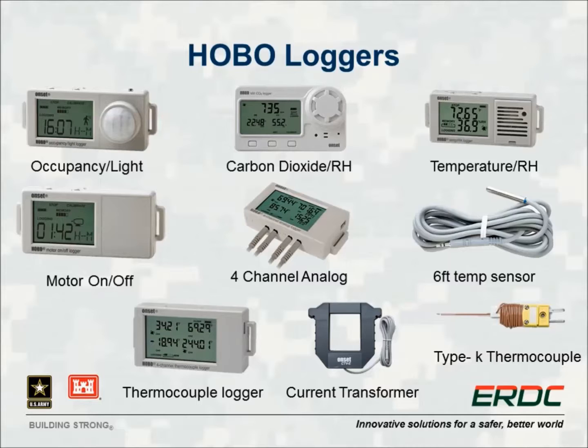It's relatively straightforward to do a study to ensure it's working correctly using a separate set of sensors, not the ones currently integrated into the building which may have their own faults, but sensors that have been recently calibrated, placed in specific locations, so you can collect that data and analyze it to confirm the economizer is working correctly. Similar studies can be done for any part of the air system, and also for water systems, to ensure they're not short cycling and that everything is working as intended.